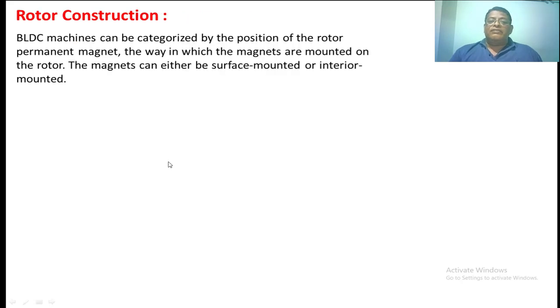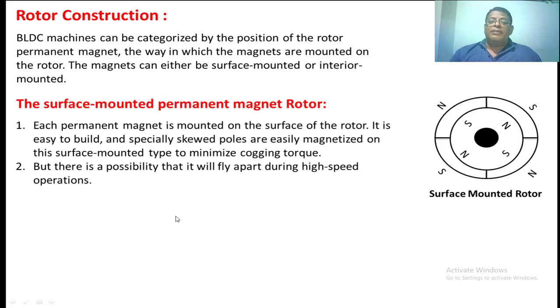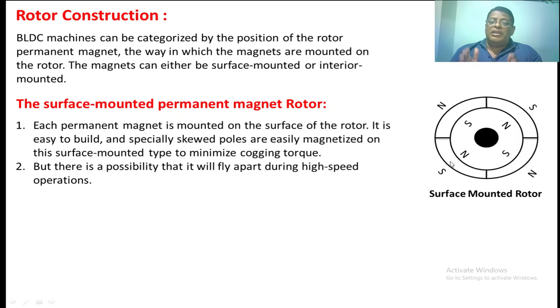In case of rotor construction of a BLDC motor, it is classified into two types. One is the surface mounted permanent magnet — the permanent magnets are mounted on the surface of the rotor. Here north pole and south pole magnets are placed around the rotor shaft. They are located in such a way that the cogging torque developed in the BLDC motor will be lesser.